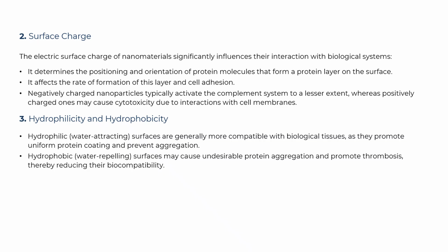Hydrophilicity and hydrophobicity. Hydrophilic, water-attracting surfaces are generally more compatible with biological tissues because they promote even protein coating and prevent aggregation. Hydrophobic, water-repelling surfaces can cause unwanted protein aggregation and promote thrombosis, reducing their biocompatibility.